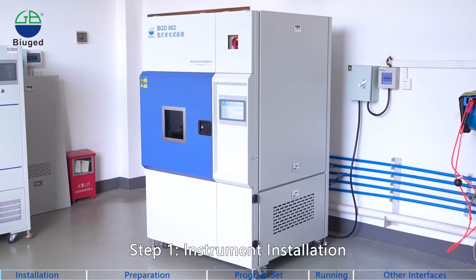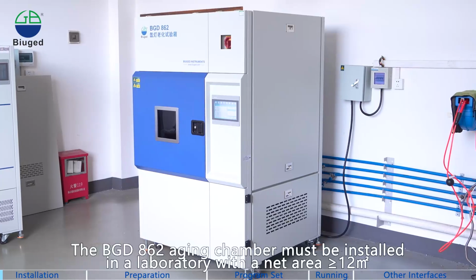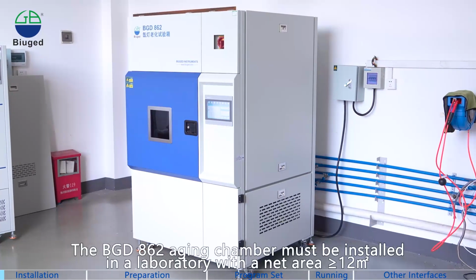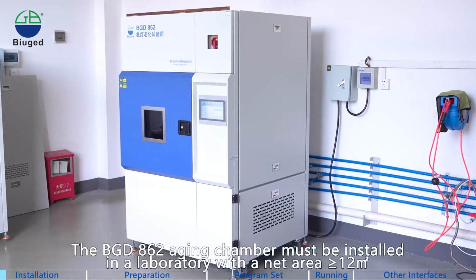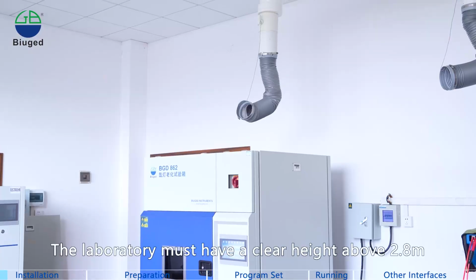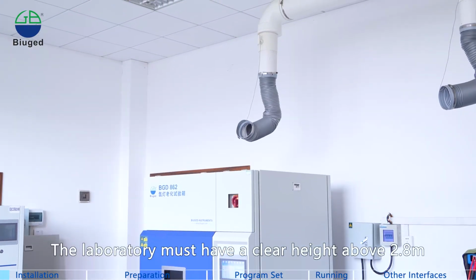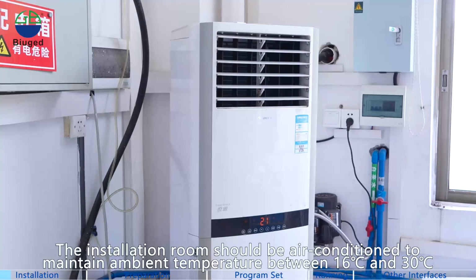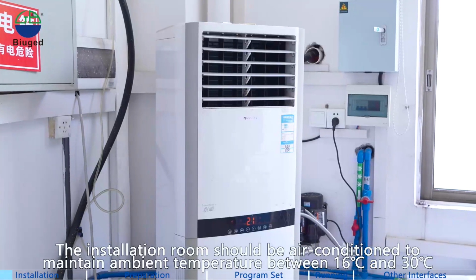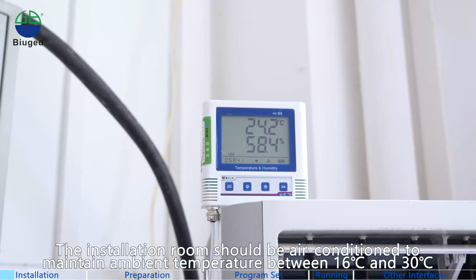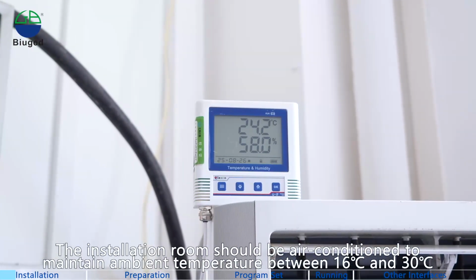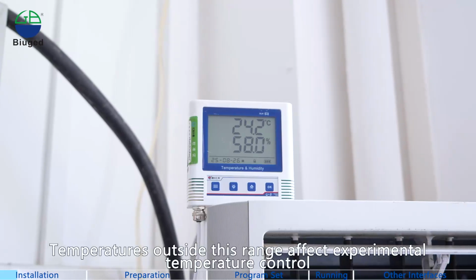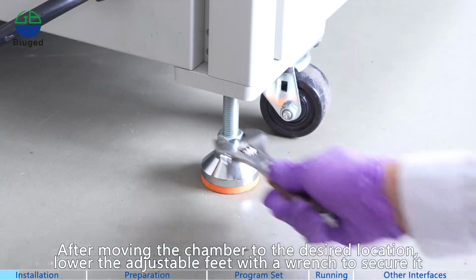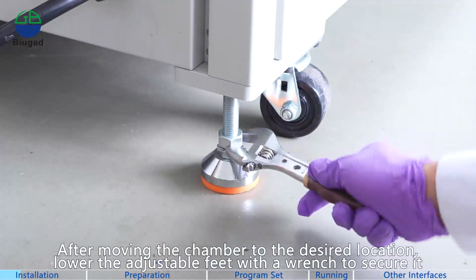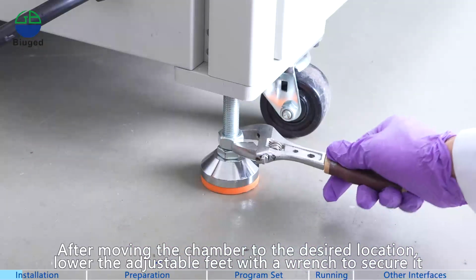Step 1. Instrument installation. The BGD 862 aging chamber must be installed in a laboratory with a net area greater than or equal to 12 square meters. The laboratory must have a clear height above 2.8 m. The installation room should be air-conditioned to maintain ambient temperature between 16 degrees Celsius and 30 degrees Celsius. Temperatures outside this range affect experimental temperature control. After moving the chamber to the desired location, lower the adjustable feet with a wrench to secure it.